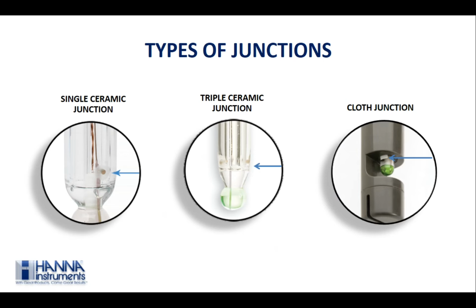Whereas a triple junction electrode means there will be three ceramic junctions on the outer side of the electrode. They are used in low conductive samples, giving out high flow rate and stable readings in low conductive samples. Even if you are using a triple ceramic junction electrode in a low conductive sample, you need to give the electrode a specific amount of time to get a stable reading.